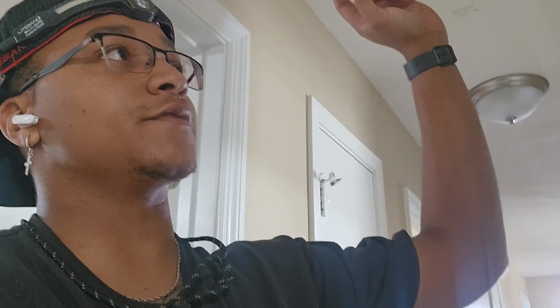What I'm going to do now is button everything back up and put my temp probe for the supply, about 2 feet up off this plenum since I can reach up there. Then I'll put my return probe in the return, and run it in heat mode to let it warm up the house.